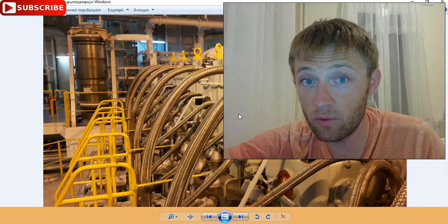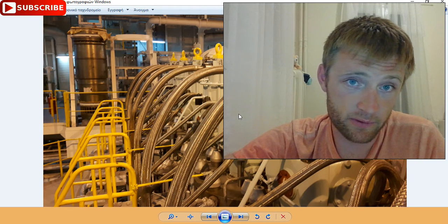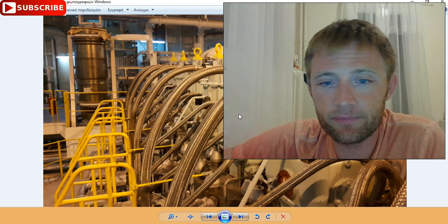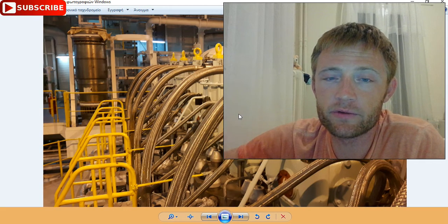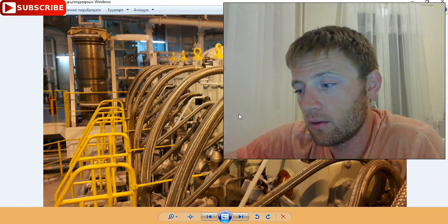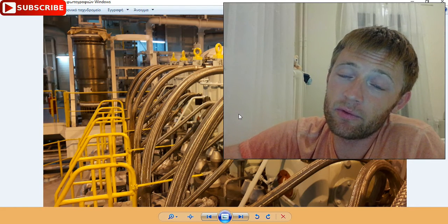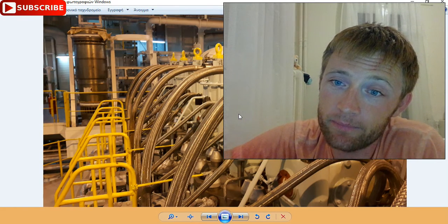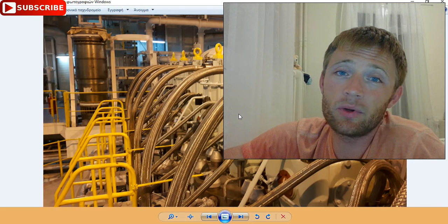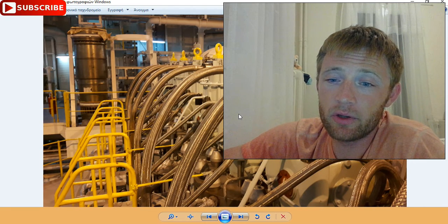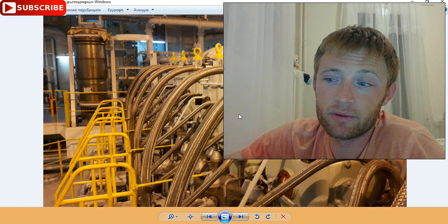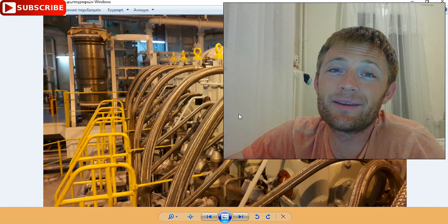And what else can we tell about O-rings? Something more interesting that I have experienced. One day there was an engineer who was looking for O-rings that must be certified for high temperature heavy fuel oil. But he could not find them, and he used one normal O-ring, not high temperature. And what happened at the moment when he put this O-ring in? This O-ring was burned, because the temperature was 130 degrees.